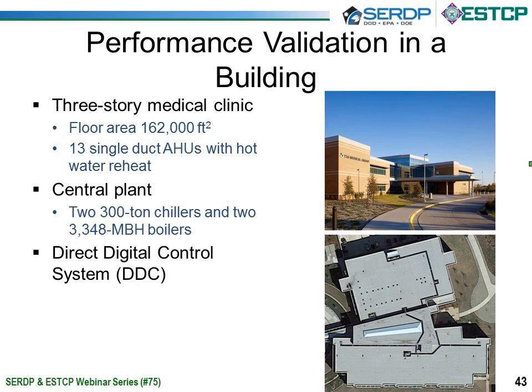So we've taken this technology and we've demonstrated it in a 3-story outpatient medical clinic at a DoD installation. You can see the characteristics here. Floor area about 160,000 square feet. There are 13 single duct air handling units with hot water reheat. The central plant has 2 chillers and 2 boilers, and there's a building management system that provides direct digital control.